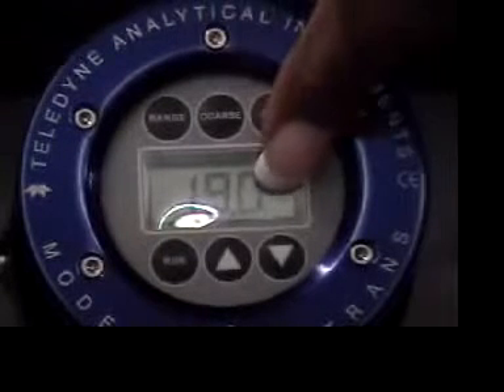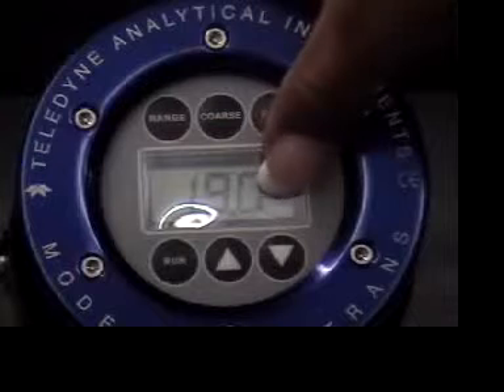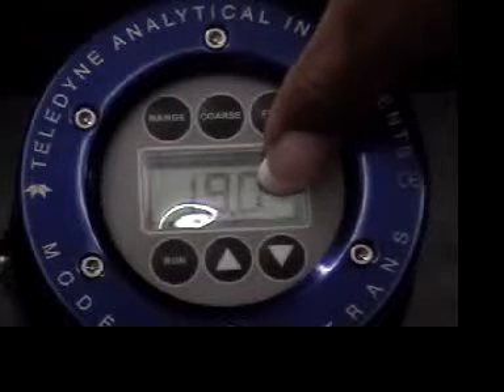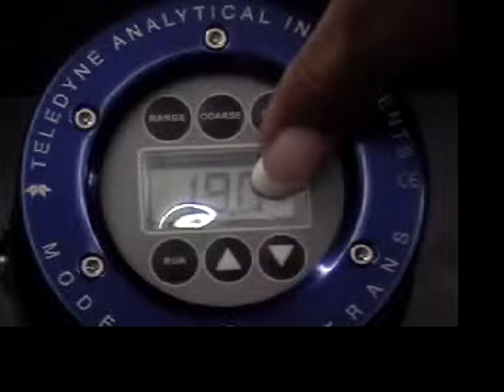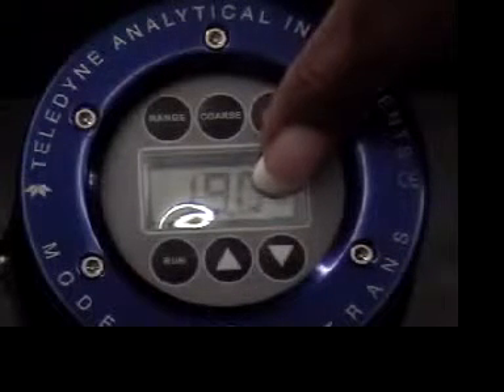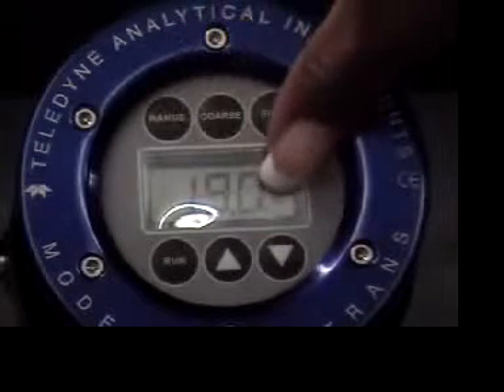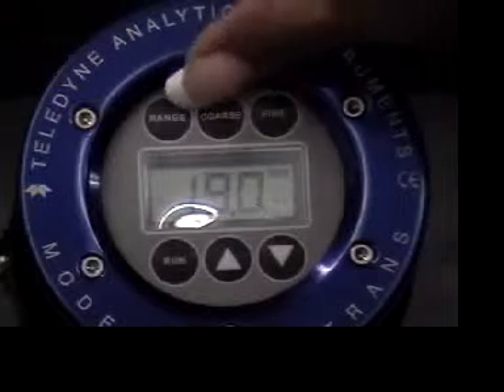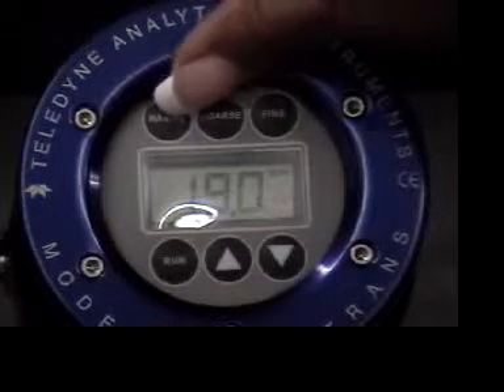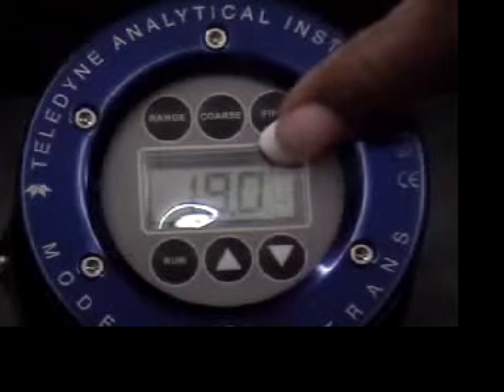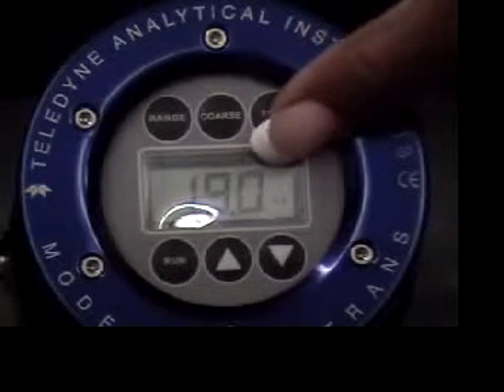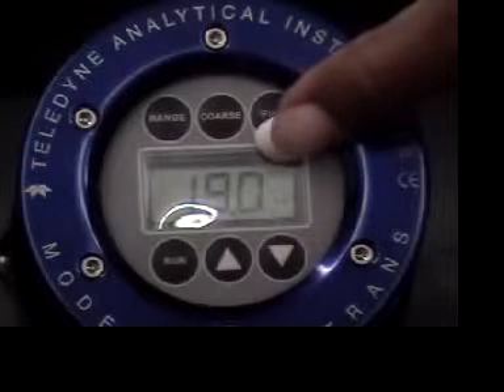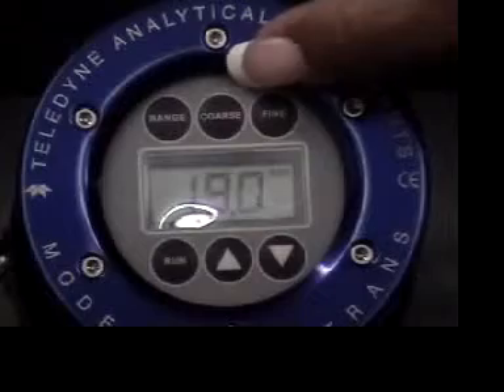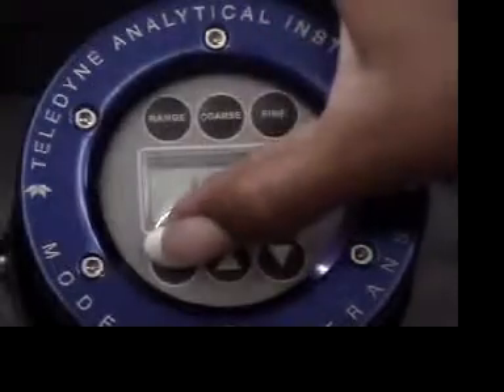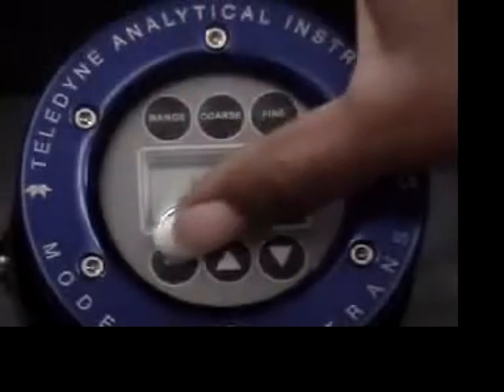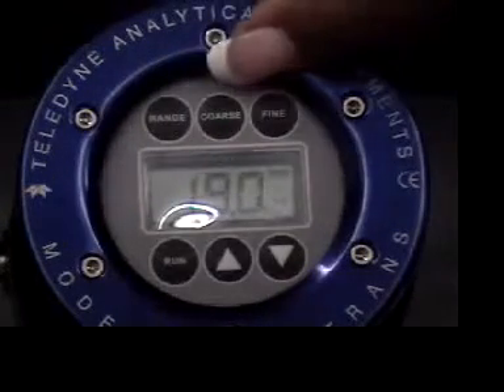Because we're measuring percent oxygen, you want to see a percent sign in the lower right-hand corner here. If you see a ppm there, you'll know you're not on the right range for percentage. So you want to press the range key until you see the percent sign come in. Right now we're in the percent range, and it's saying RUN because that's the normal operation designation. To start a calibration, press the run key to make sure you're in the run position.